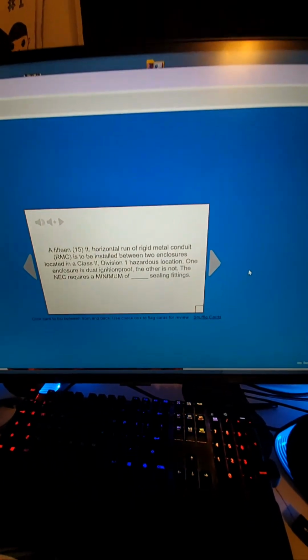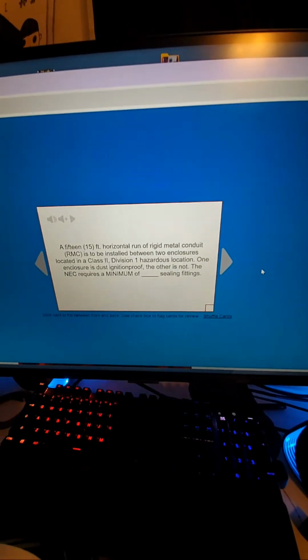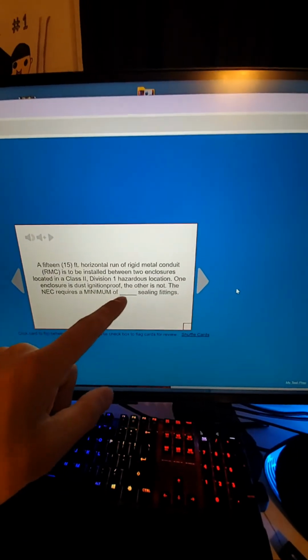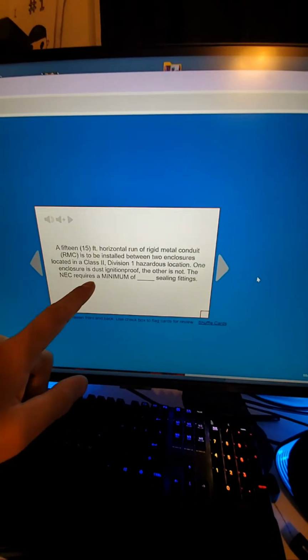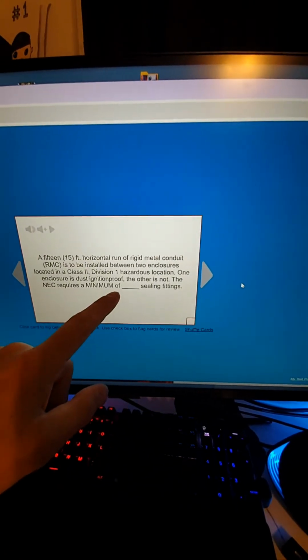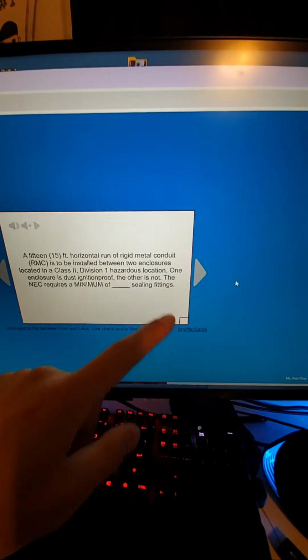What's next? A 15-foot horizontal run of rigid metal conduit can be installed between enclosures located in a Class 2 Division 1 hazardous location. One of the enclosures is dust ignition proof, the other is not. The NEC requires a minimum number of blank sealing fittings.